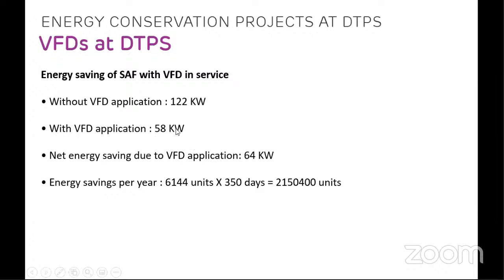If we had not installed the VFD, the motor would have run at the full 122 kilowatt and power would have been lost across the damper, which was throttled to almost 50%. With VFD, we open this damper 100% and throttle the speed of the motor rather than throttling the flow. So the motor gives lesser flow, which meets the process requirement. From this, we get energy saving of 6144 units for 350 days, which is 21,50,000 units. So you see, a huge amount of energy savings can be gained by installing variable frequency drives for different motors.